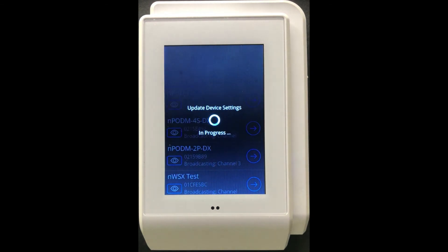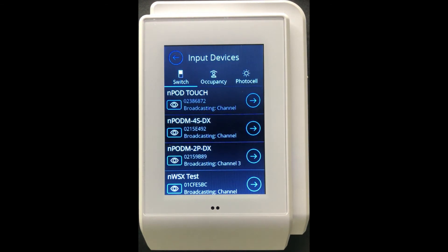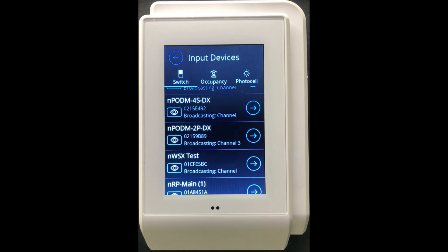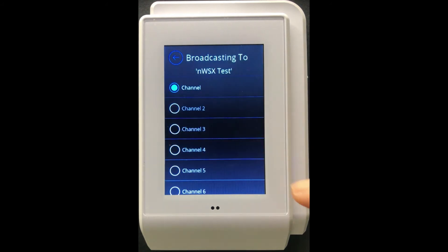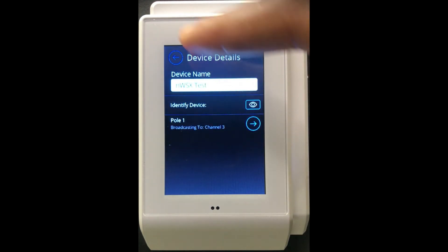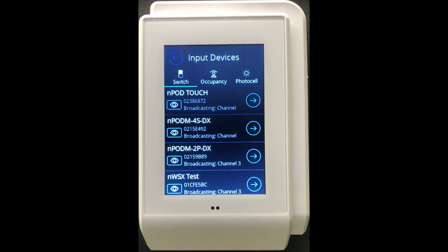So we've modified this particular nPODM-2P-DX, and as we press the back button all those settings are pushed directly into that switch. Similarly, we can come in and look at the NWSX. The NWSX contains both a switch input as well as an occupancy sensor input and a photocell input. By editing this NWSX here, you are specifically editing the switch portion, so you can modify it to broadcast to channel three.